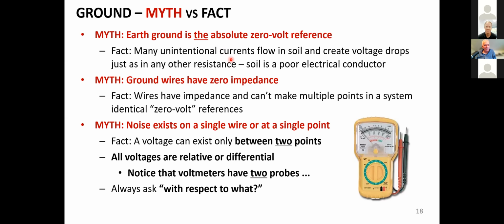But it also means the voltage drop on the neutral conductor as it goes through your neighborhood is superimposed on all these ground stakes. So if you drive a stake in the ground, you have no idea where you are in this network of voltage dividers created by the utility company.